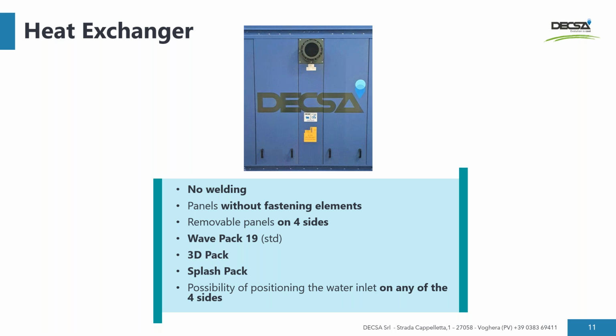Heat exchanger section. This is maybe the core of this cooling tower because it's very interesting how our designer did it. I mean, the panels are fixed on the cooling tower frame without any fastening element. This is very important from a maintenance point of view because it's very easy to remove these panels. To remove them, you only have to lift them up and pull back because, as you can see in the picture, the panels are supplied with handles. So it's very easy to open them and have access to the fill pack for maintenance and cleaning of it. The panels are fully removable on the 4 sides of the unit.